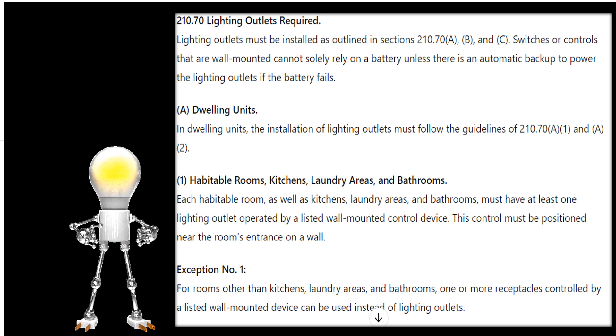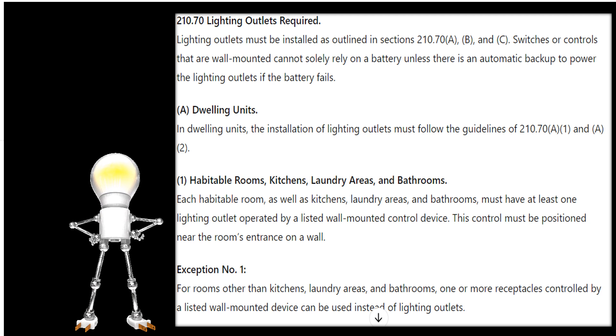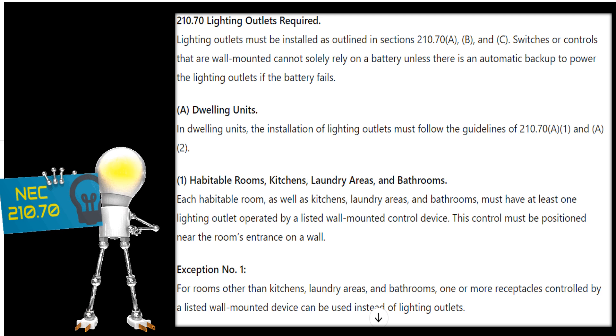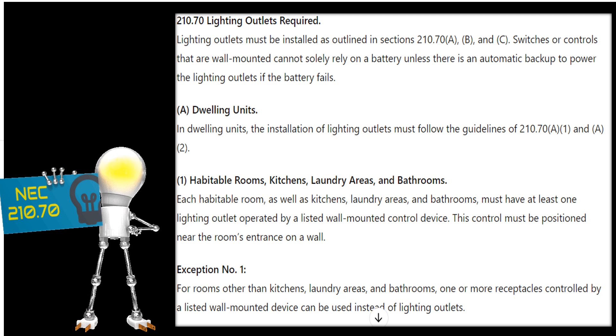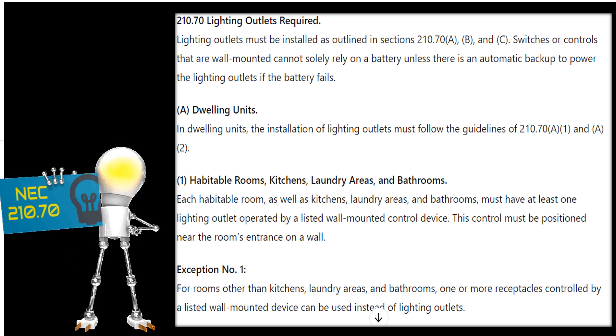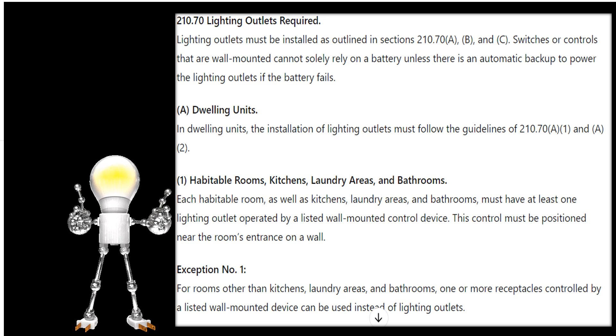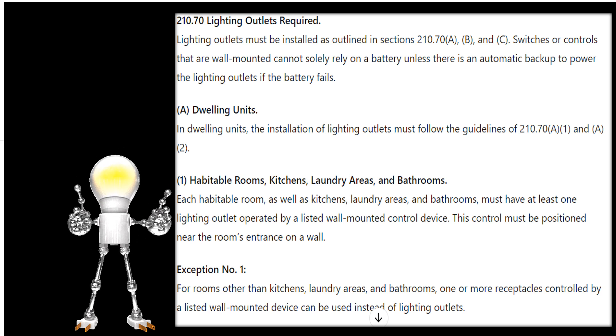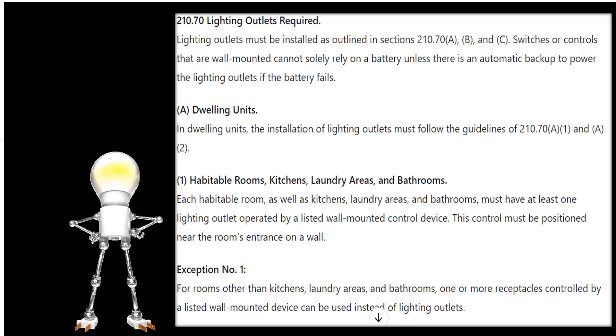One thing to watch out for: in this 2023 version, they've added laundry areas. In previous code cycles, it was only required to have actual lighting outlets in kitchens and bathrooms. The reason behind the code is so you don't have switch-controlled receptacles in a kitchen or bathroom — meaning you'd have to plug in lamps just to get light. The same holds true in the laundry area; we don't want lamps just to fold laundry. The 2023 cycle recognized this needed to be added, and it's an excellent addition.